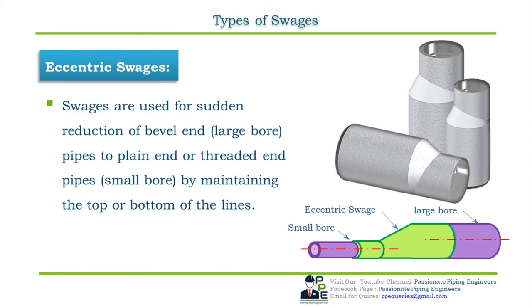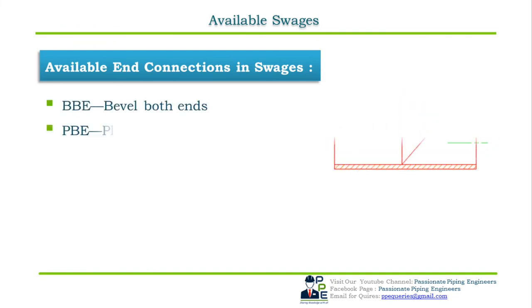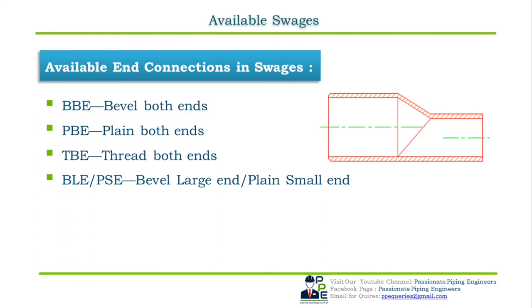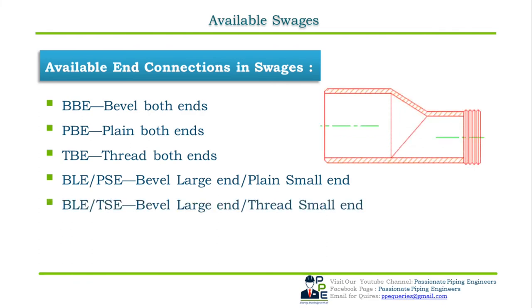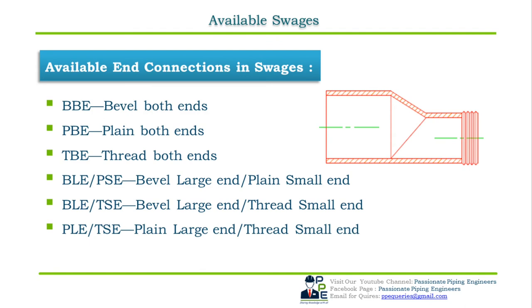Eccentric swedges maintain the side of the pipe — whether top or bottom — and are available in butt welded, socket welded, and threaded configurations. The available end preparations for swedges are: BBE (bevel both ends), PBE (plain both ends), TBE (threaded both ends), BLE/PSE (bevel large end / plain small end), BLE/TSE (bevel large end / threaded small end), and PLE/TSE (plain large end / threaded small end).